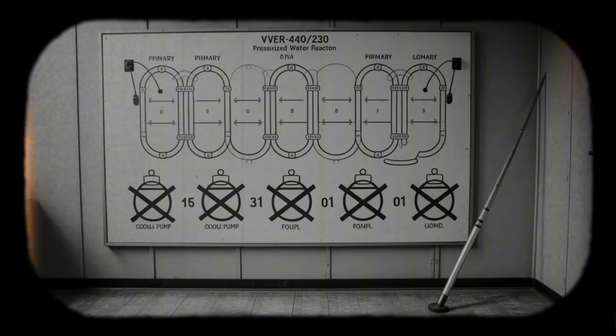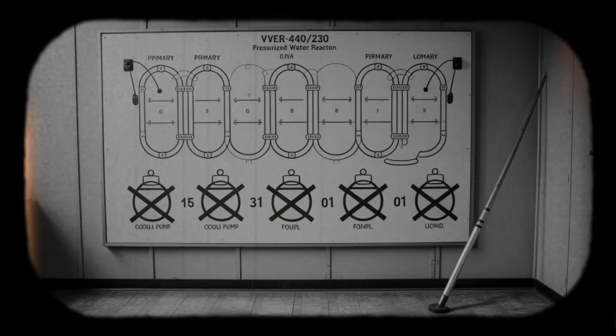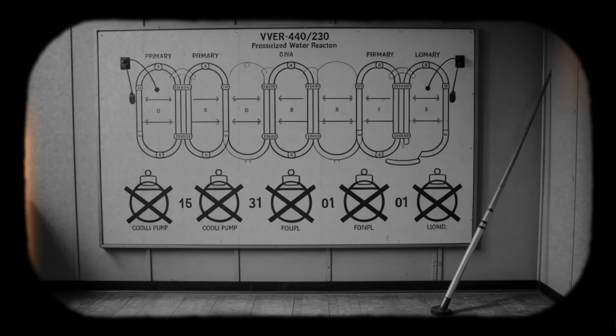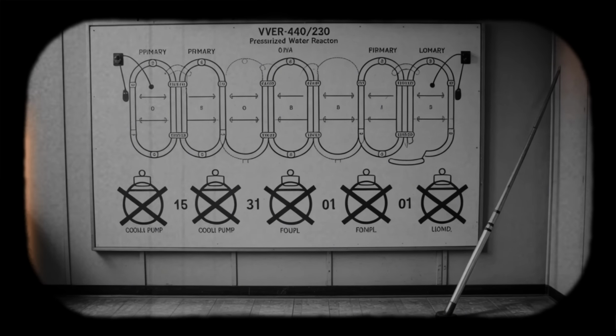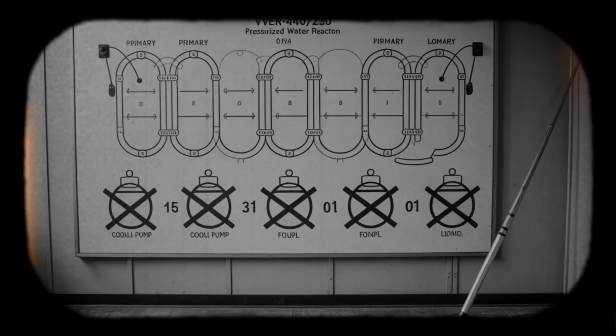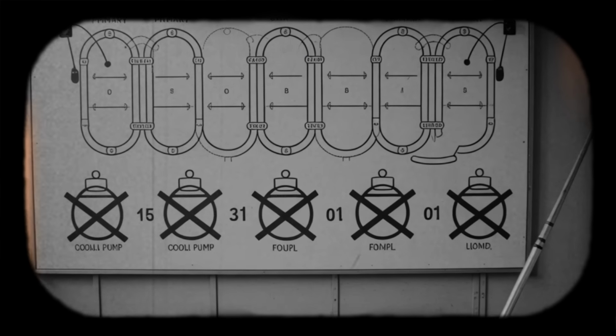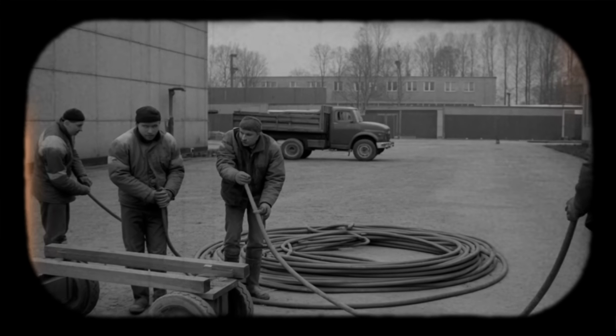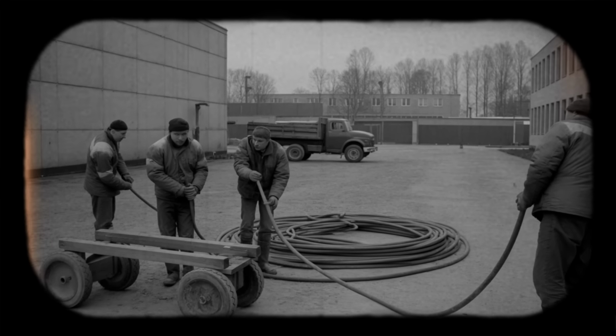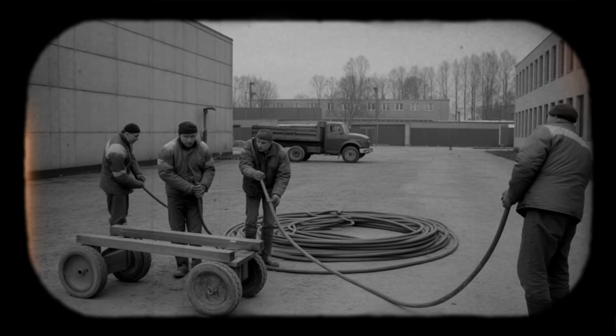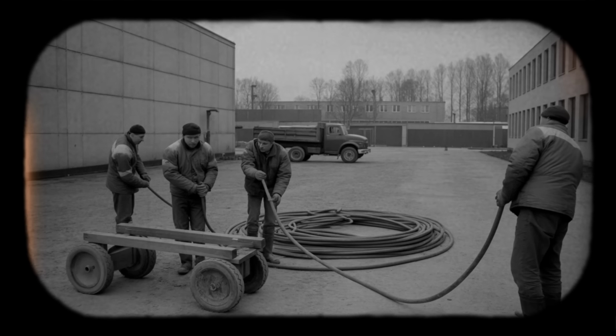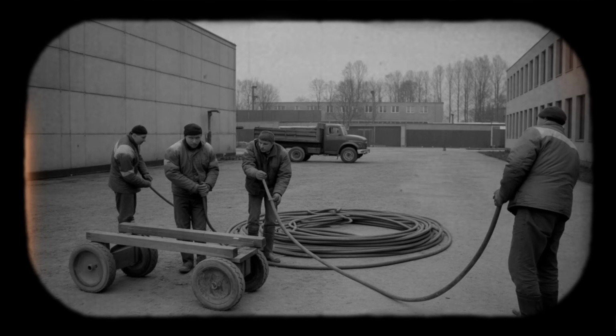Yet survival of the Greifswald core depended on actions that fell outside procedures. The use of boron injection pumps as a makeup and cooling source was not a procedurally guided response. Cross-connecting power from Unit 2 to Unit 1 had no written instruction. These were on-the-spot engineering judgments, using equipment outside its design basis, connecting systems never intended to be linked.